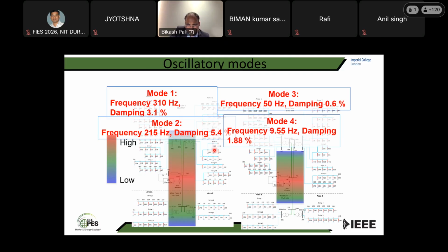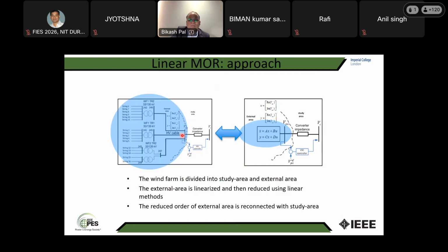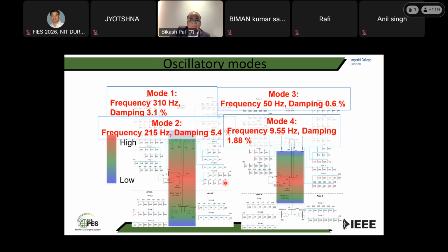So for a 1,000 megawatt wind farm connected to the grid at, say, a 400 kV substation, the wind farm itself has to be a simplified model. So how do we do that? We do model reduction. This is the wind farm, and this is the converter side. Why? Because the red means this is the area that participates more in this mode.